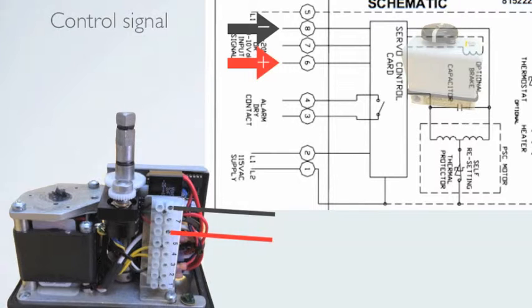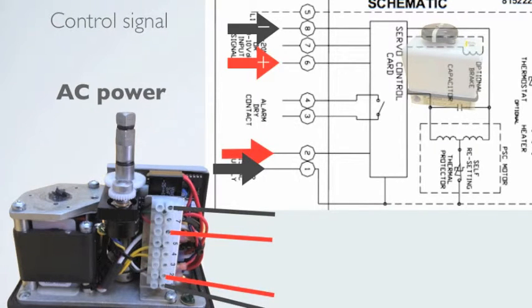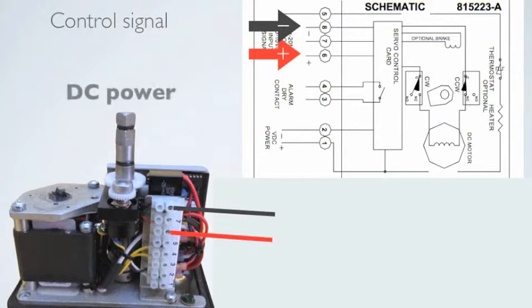Now wire your supply power to the unit. For AC units, put the neutral on number 1, the hot on number 2. For DC units, put the positive DC on number 1, the negative DC on number 2.